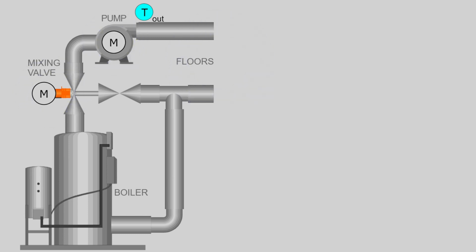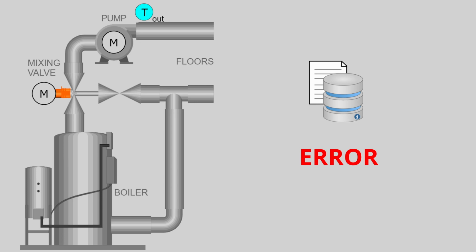The construction phase. This system was found to have 5 use cases. It has to control the pump, control the outflow temperature, and control each individual valve that opens and closes the loop going out to each individual room. The more underlying use cases are the handling of data and error messages. The first and most important use case was selected to be the control of the mixer valve, as it controls the source of heat to the floors.